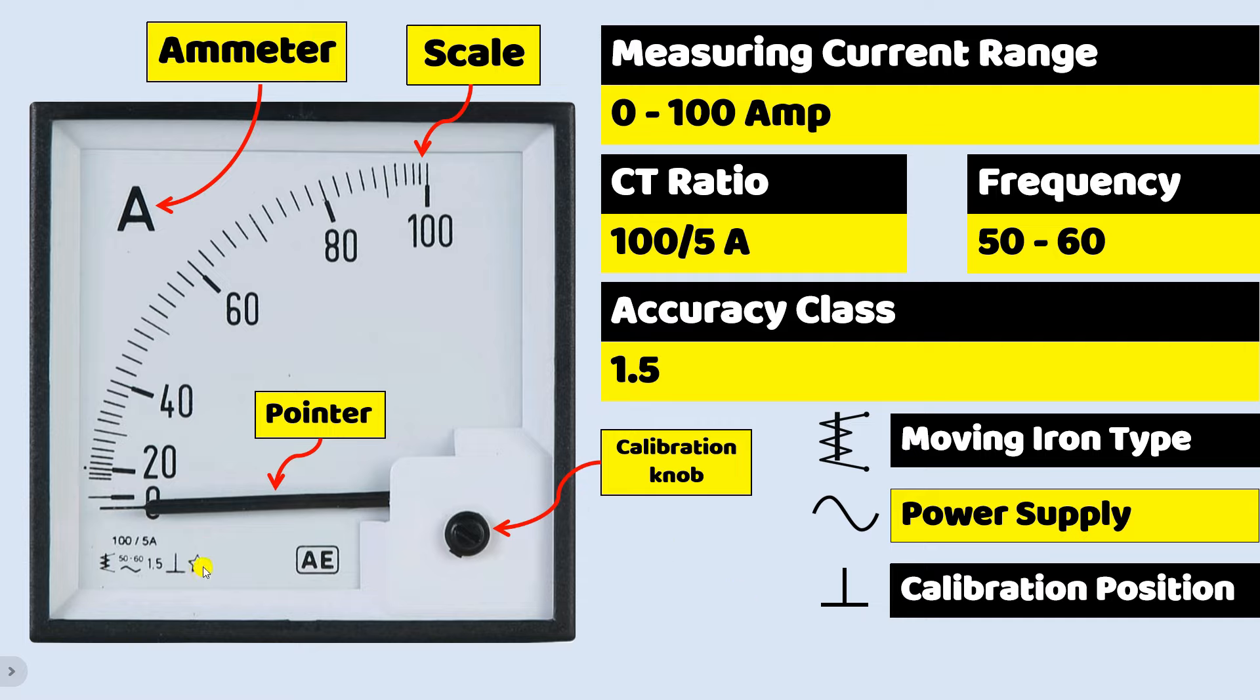Apart from this, you can see this star symbol here. It has two written inside it. It means dielectric test. It means how much voltage is provided to this ammeter and tested it. This detail is given here. If two is written here, it means that it has been tested at 2000 volt.